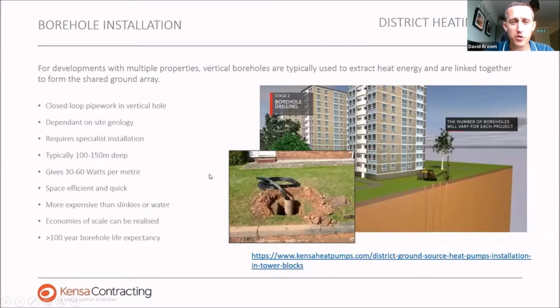In terms of the infrastructure that goes in the ground, the vast majority of projects we install use closed loop vertical boreholes. We'll typically drill holes anything from 100 to 150 meters, but in denser applications, so suburban and urban settings, and where we're looking at high-rise tower blocks, we've recently been installing systems with boreholes from around 200 to 220 meters in depth.